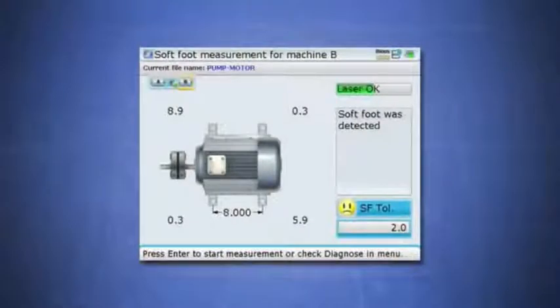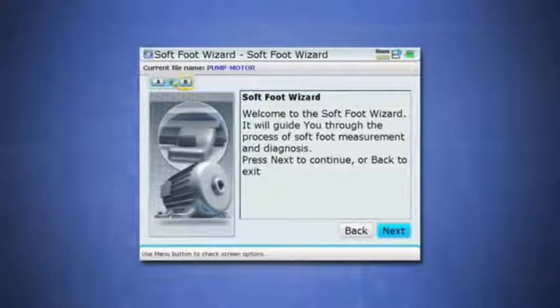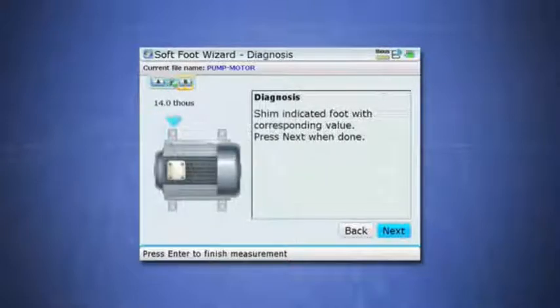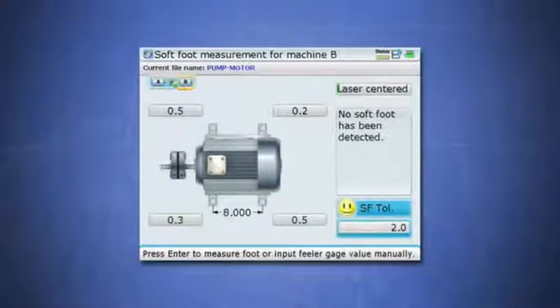If you don't have years of experience with softfoot, the Rotalign Ultra's Softfoot Wizard will help you. The Softfoot Wizard is your highly experienced field companion that walks you through the process step by step, guiding you graphically through the most efficient techniques of softfoot correction. It diagnoses your problem and solves it with instructions that are very clear and easy to understand at all experience levels. Once you complete the Softfoot Wizard, the final value should be less than 2 mils, which means the softfoot has been removed. With this taken care of, you can now finish the rest of the alignment.